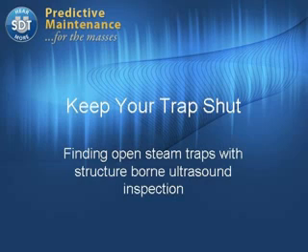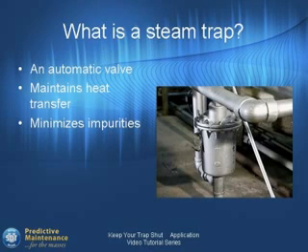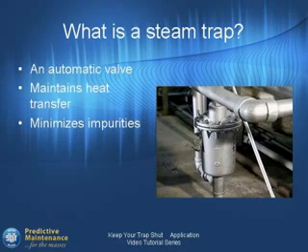Some examples of steam trap data collected during surveys will illustrate what you should be listening for. A steam system is a collection of components that deliver steam from a boiler to the point of use and back to the boiler. The design and installation of the system impacts how efficiently steam is transferred from point A to point B. The goals are minimum steam loss, maximum transfer of heat, and timely removal of condensate and non-condensable gases.